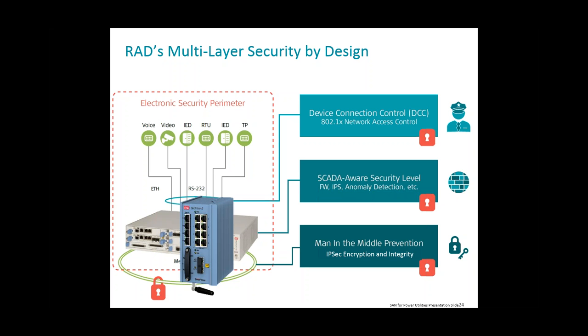It essentially gives you the same kind of protection that MACSEC does. The only real significant difference between MACSEC and IPSEC is that MACSEC is hardware-based, so it's very low latency. It only adds, in the case of our Megaplex product, about 8 microseconds of additional delay to the entire payload when encrypting it, whereas IPSEC can have tens of milliseconds of additional delay. So that could be undesirable for teleprotection with IPSEC, but MACSEC is perfect.